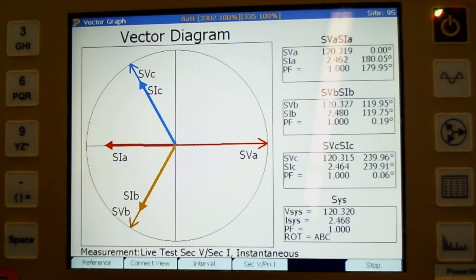When I look at that vector, I see that on A phase, my red vectors, I have polarity reversal. I'm 180 degrees out there. Down here, this is showing my secondary voltage and secondary current, because I can hit this button and change it to primary current if I like. Right now I'm looking at the secondary side.